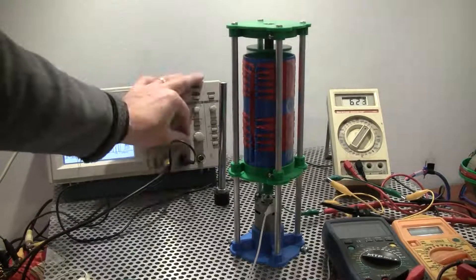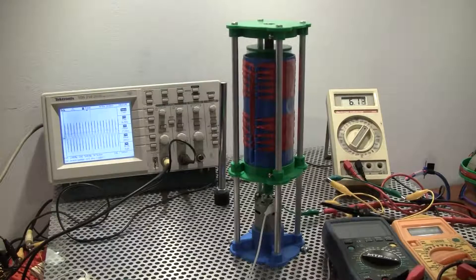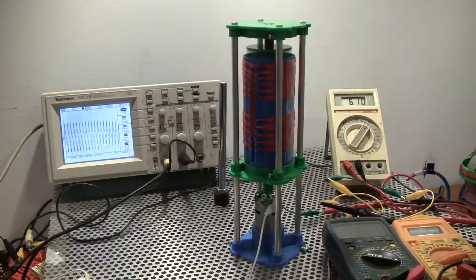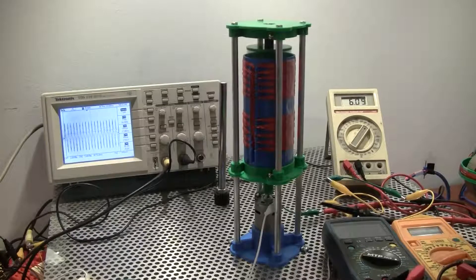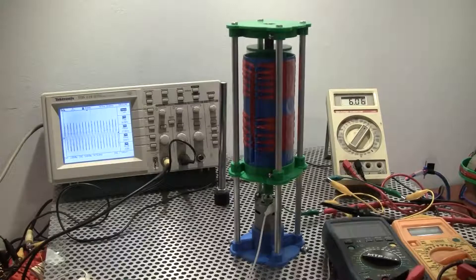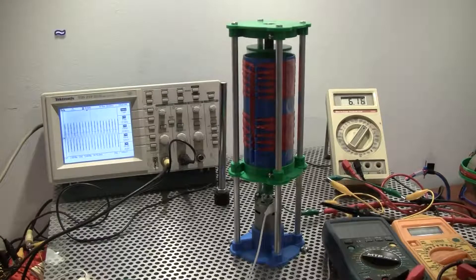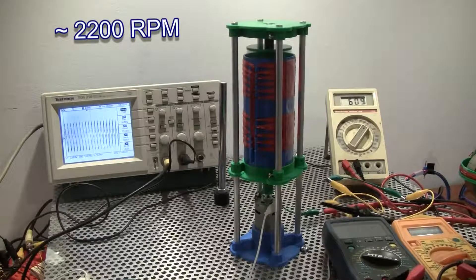It's at maximum velocity, 5 volts per division, so we're at about 25 volts AC output, 36.5 hertz. We multiply that by 60 to get the RPM.